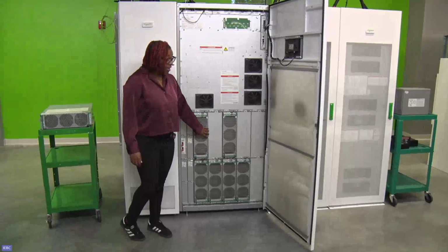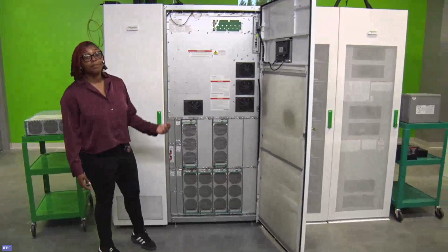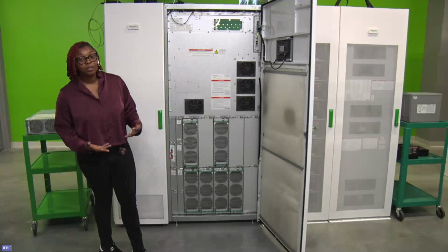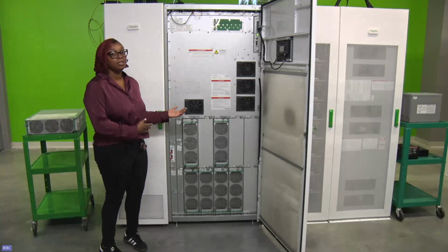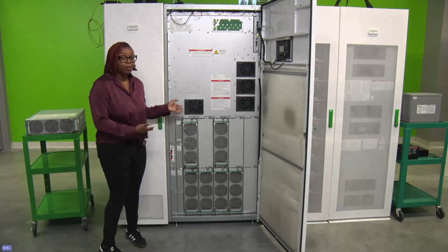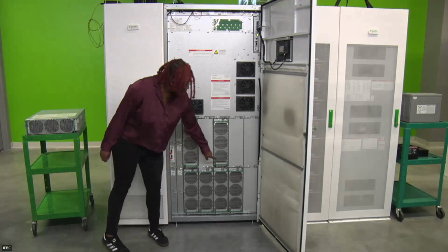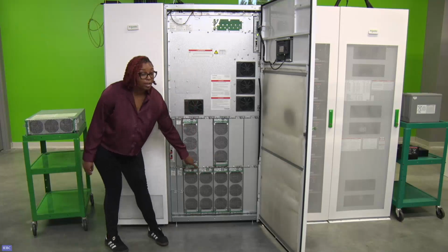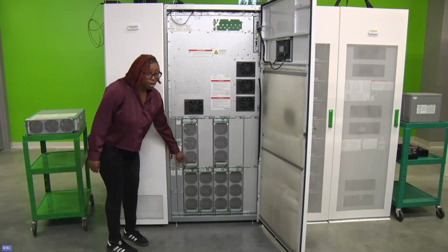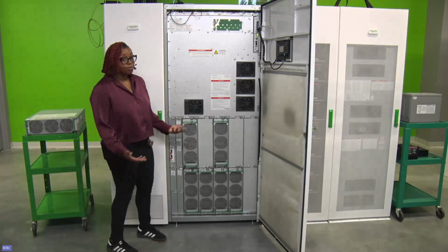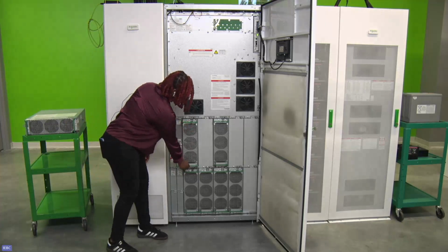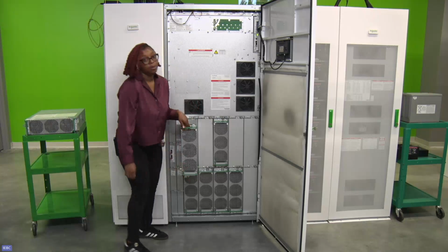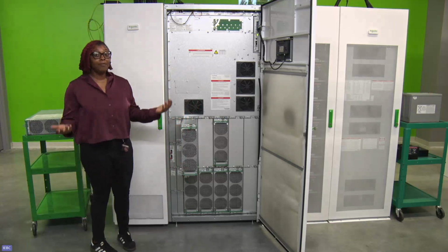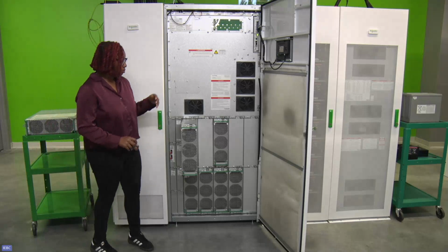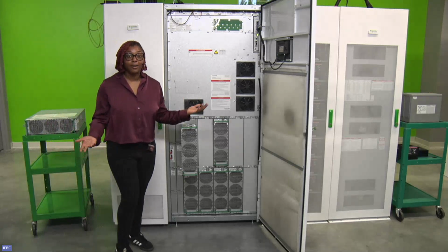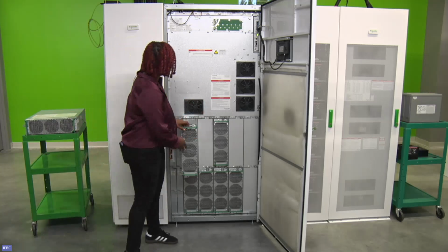Something that's really nice about these power modules is that they are live swappable. What that means is qualified personnel dressed in proper PPE can actually walk up to the system while it is energized and swap out, add, or replace power modules. Everything here with the green light is currently on and energized, but this one is off, and I can demo what a live swap looks like. What you would do is press down on this green lever and then just pull this right out. That takes maybe 5 to 10 minutes to swap these out and completely eliminates downtime, which saves a lot of money in the long run.